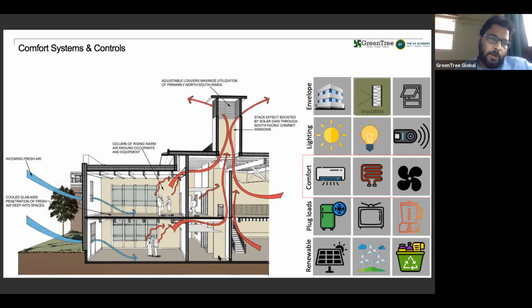Certainly the COP, or coefficient of performance, or efficiency of the systems improves, and based on the system design, building size, and usage of the building, these systems can be selected. For example, if there's a meeting room which is not very often used, you can use the best efficient non-centralized system, maybe a 5 star rated SPTAC, instead of a water cooled chilled system which is also serving other components. Meeting rooms, being spaces not regularly used, can be plugged with SPTACs instead.